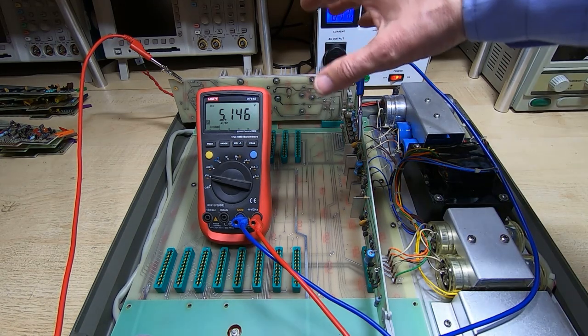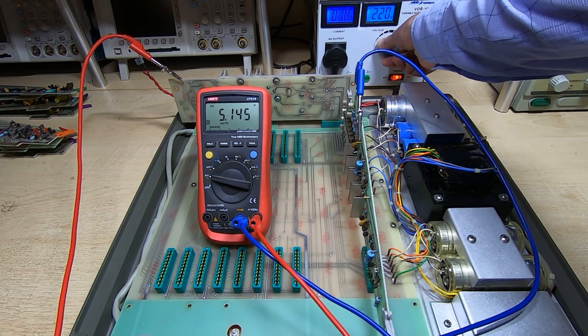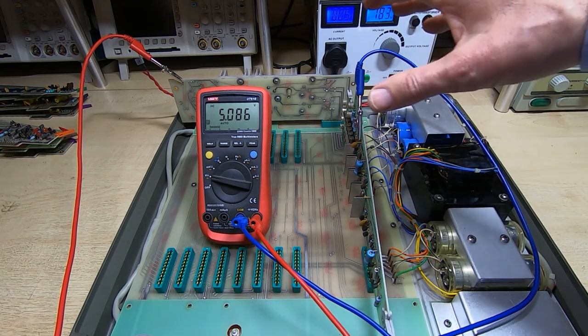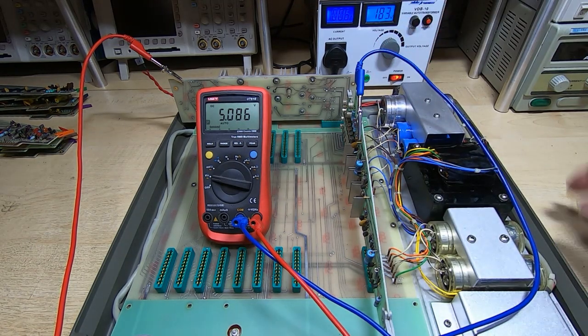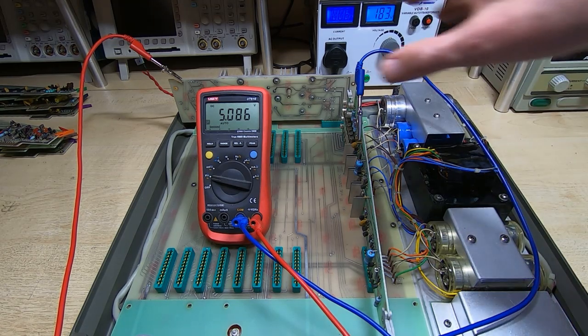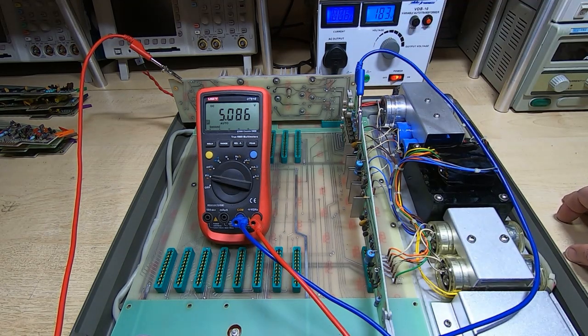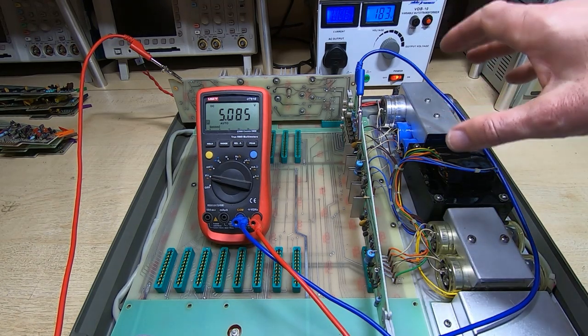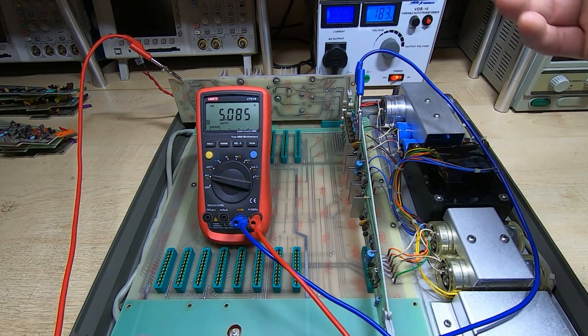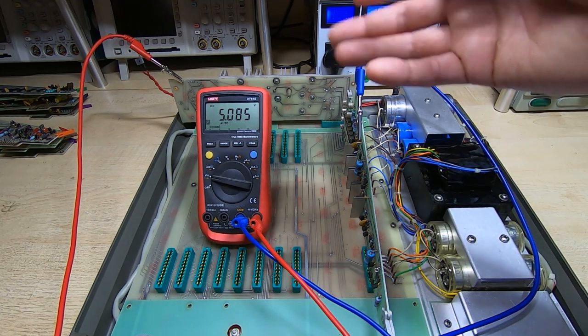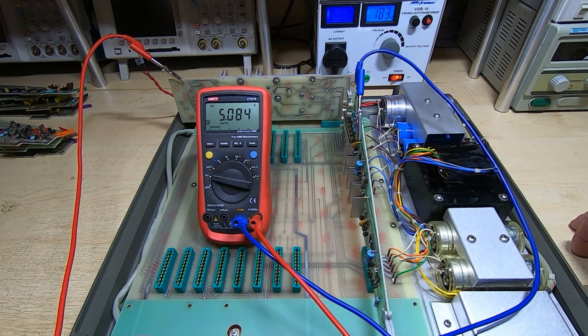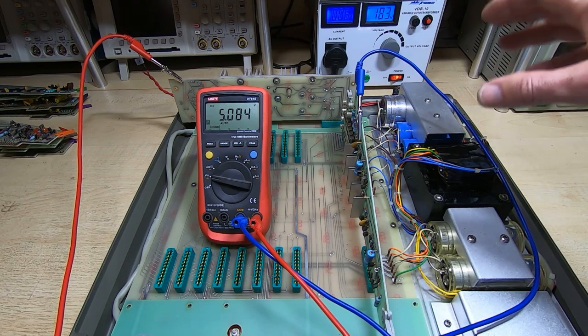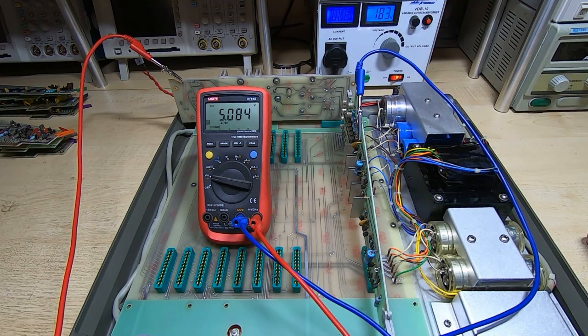It will be slightly high because there's no load on it, but what I'm going to do is leave this on soak now. I'll probably leave this overnight with a fairly low load on it, about 50% of its normal load. The reason I do this and leave it for so long is because quite often you find these units actually work until there's an issue with the power supply, which is where most of the faults develop, and quite often they'll damage the other boards, and then it's a lot of work to get those sorted out.